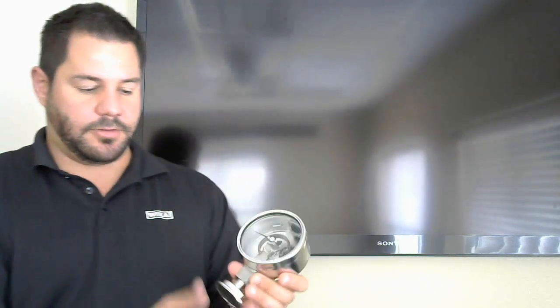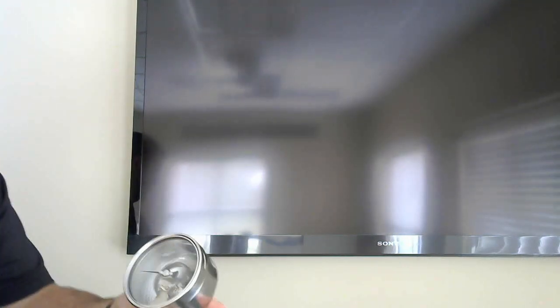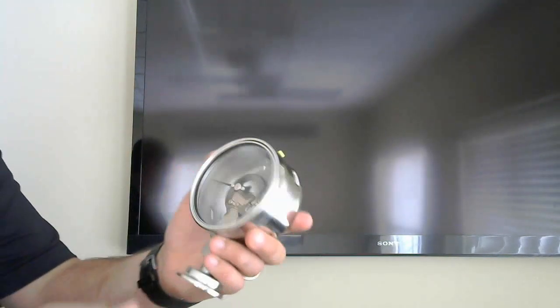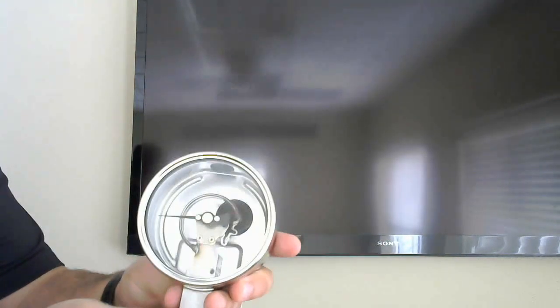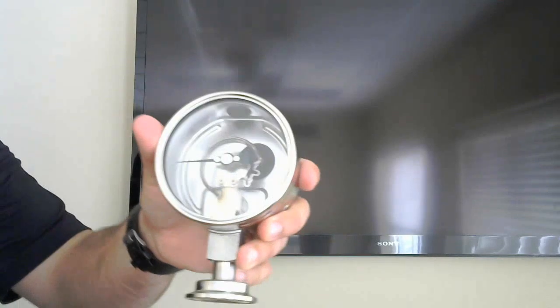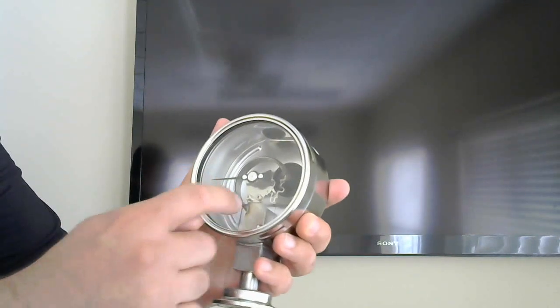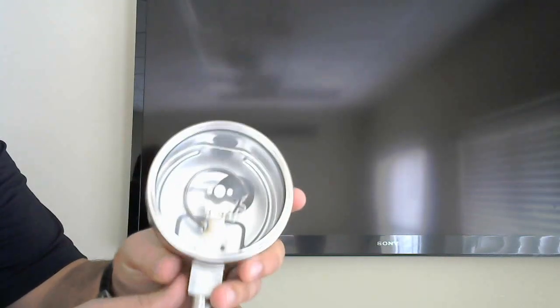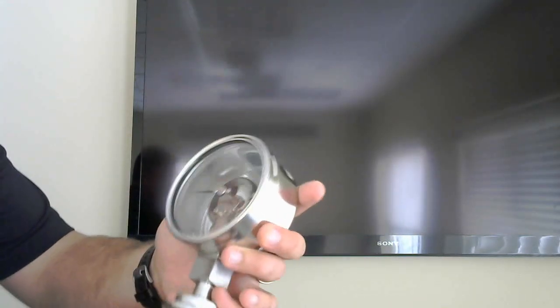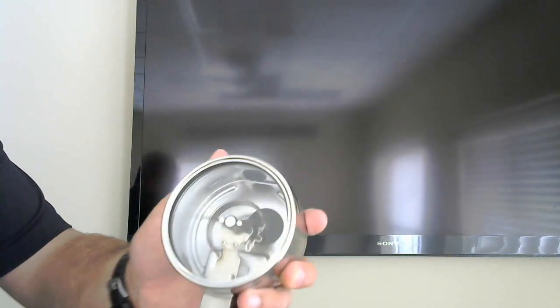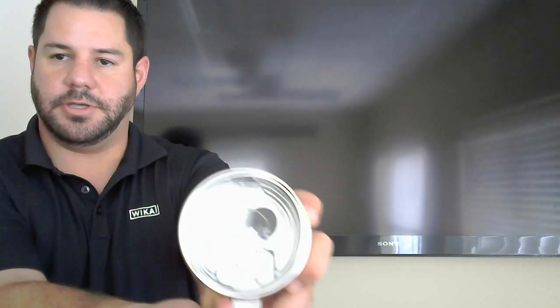So what WIKA did - this is WIKA's basic pressure gauge, your standard diaphragm pressure gauge that you'll see in every facility. Here's your diaphragm with the standard fill fluid in the Bourdon tube. As you push on the diaphragm, it makes the gauge read, moving the needle - though mine's been pushed so many times it hardly moves anymore. That's how a pressure gauge works, and this is our standard gauge that we'd sell up against any competition.